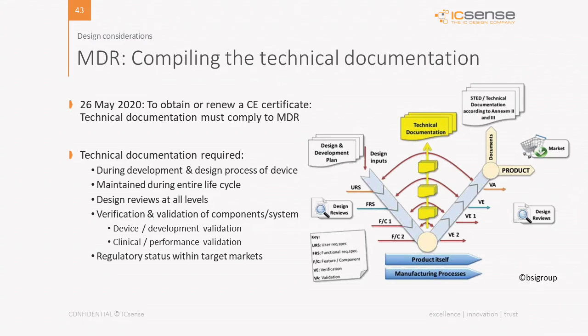Before placing a medical device on the European market, manufacturers need to produce a lot of technical documentation providing the evidence of conformity with this legislation. Technical documents need to conform with the existing MDD or the Active Implantable Medical Device Directive. As of May 2020, a new regulation will come into force, and for manufacturers to obtain or renew their CE certificate, this technical documentation will need to comply with this new medical regulation, even if they have been on the market previously.